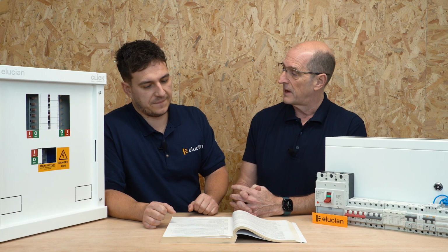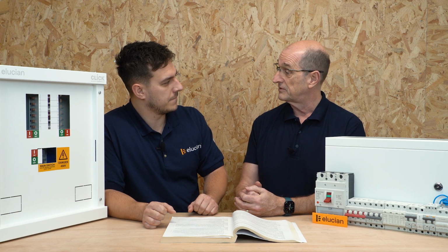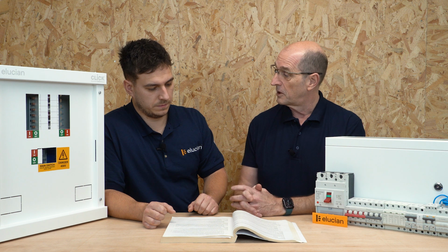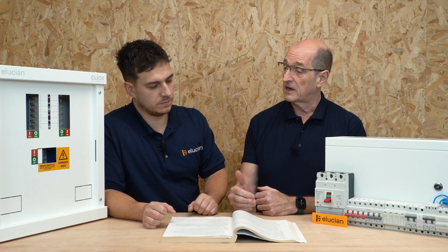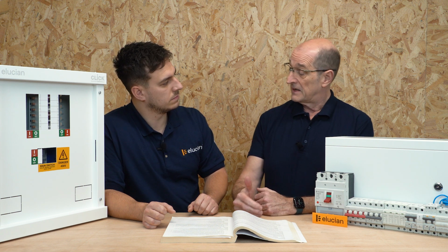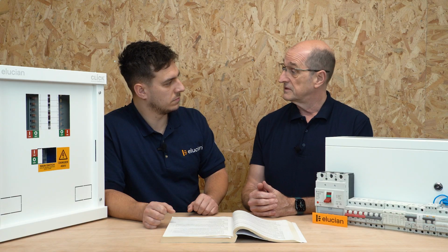I mean, generally they're going to look at the price. And the problem with selecting by price is you're always going to go for a Type AC and think that you've picked something appropriate, when in reality the connected load may require an F or a B and something to take account of the DC current that exists or the increasing frequency that exists. Okay. And particularly, again, we touched on the emerging technologies.